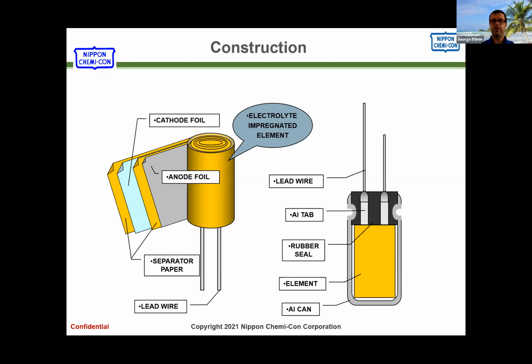So what tends to happen during vibration with electrolytic capacitors: if you imagine a side-to-side movement, the outside body will move to the left, for example, until the movement limit is reached, then it starts moving in the opposite direction. The problem is the element still wants to move in that direction - it's kind of like a crash dummy. So you get a lot of resonance, a lot of internal damage from the element hitting the can.